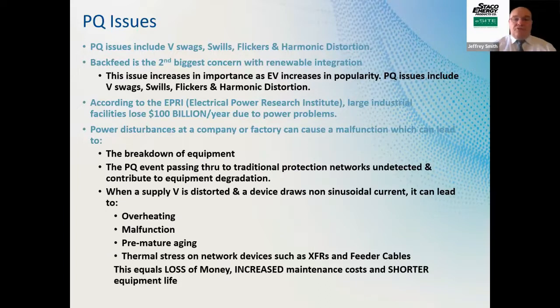Power quality issues that we talked about were sags, swells, flickers, harmonic distortion. Backfeed is the second biggest concern in renewable energy. We're looking at different systems out there that can help us minimize these sags, swells, and flickers because this is going to be put back onto the utility in these areas. And we want to make sure that we're not causing issues for other areas. And for the existing loads, we want to make sure that the existing loads have a nice, good sine wave for the products that we're working with.